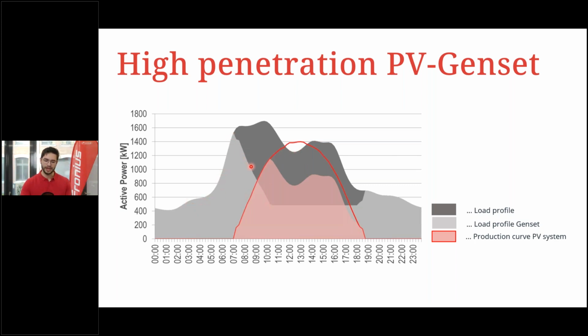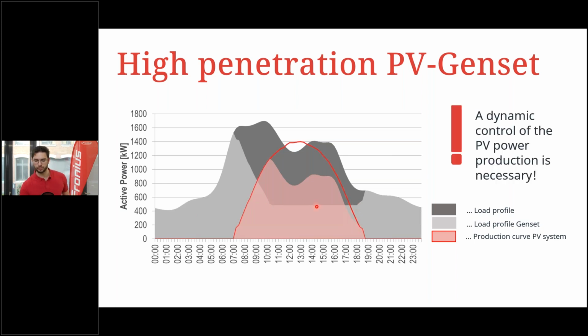So the light gray area would be the energy out of the generator, and the dark gray area would be supplemented by the PV system. So the red curve equals the dark gray area. And as you can see, at some point around noon, we have so much energy because the sun is at the perfect position for the PV system. And then we need to regulate down the output power of the inverter in order to leave the genset on a minimum load. This would be the straight line at the bottom here. So in a high penetration system, a dynamic control of the PV power production is necessary. Otherwise, we would have a backflow and it could destroy either the inverters or the generator. Of course, not good.